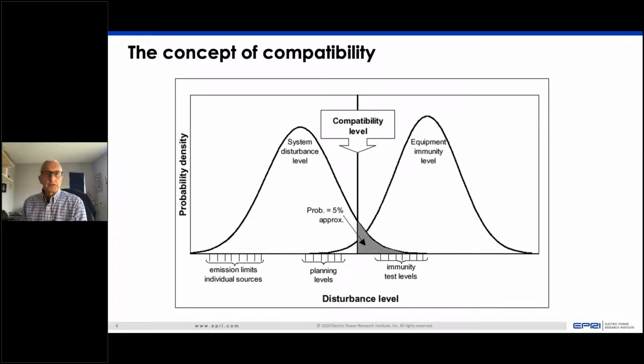And I think what I'll do is just use two examples of historical investigations, one on harmonics and one on voltage sags, to illustrate these concepts of compatibility in two different categories of power quality disturbances. One category is what I call steady state disturbances, or power quality variations that are there all the time, like voltage variations, flicker, and harmonics. And then disturbances that are based on individual events, like faults on the power system that result in voltage sags or lightning transients. We use harmonics and voltage sags to illustrate those two categories of how we've worked on this historically.